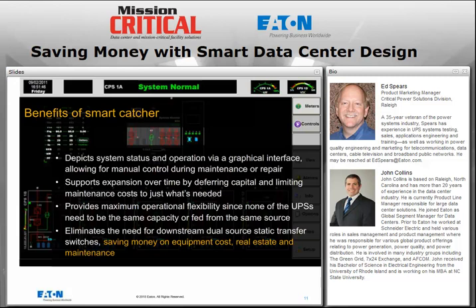It also eliminates the need for downstream dual-source static transfer switches. If you're familiar with catcher systems, you know that those are frequently deployed, and while they do the job, it does add a significant amount to the upfront cost, and it's not just the upfront cost for the static switch equipment. There's also the real estate, typically on the data center floor, and maintenance and repair costs for those devices. Basically, it's a good idea to reduce the dependence on any switch if at all possible. That doesn't mean there's not fast switching involved in a smart catcher system, but we use the internal static switches that are built into every UPS to provide this kind of thing.